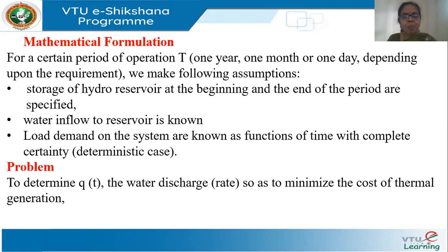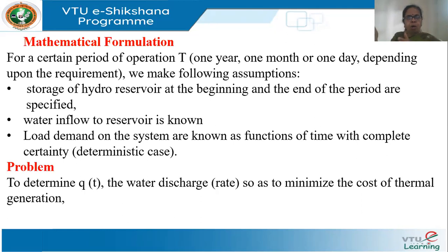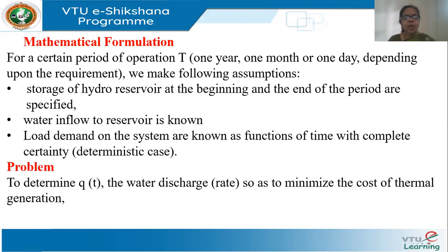The problem statement: I have a period of operation T, say one day, divided into equal intervals — for example, one-hour or eight-hour blocks. The problem boils down to determining the water discharge rate q(t) at each sub-interval so as to minimize the cost of thermal generation. This solution will also tell me what the hydel generation and thermal generation are at each sub-interval.